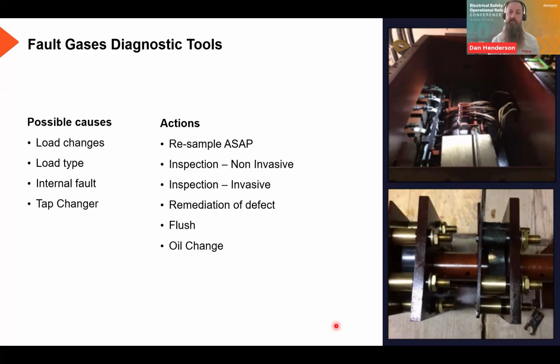But again, this is a massive contributor to essentially overloading the asset, which results in an internal fault given away by the DGA results. With internal faults, the design has been very similar for a long period of time. Transformers are a good design and quite robust, but there are parts in there that can fail over time. The tap changer is probably one of the lead contributors on most occasions when I've had sampling done and something's come back with a thermal fault in the transformer. Although they're quite substantial, there are some less substantial parts on there. It's essentially a rotating cam between contacts, as shown in the pictures.